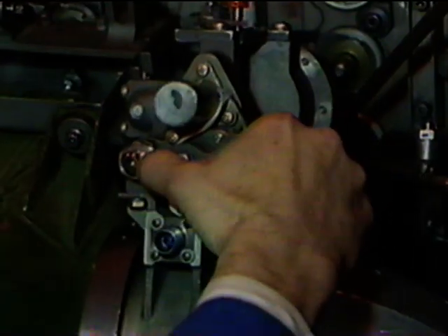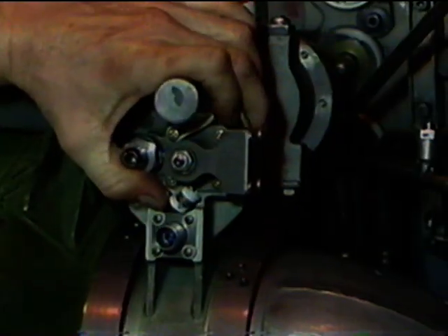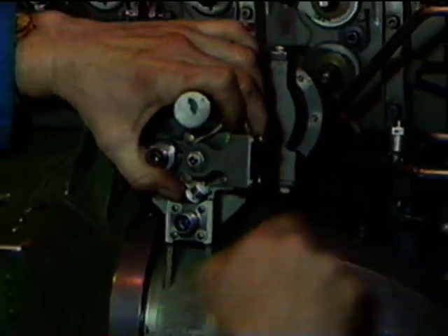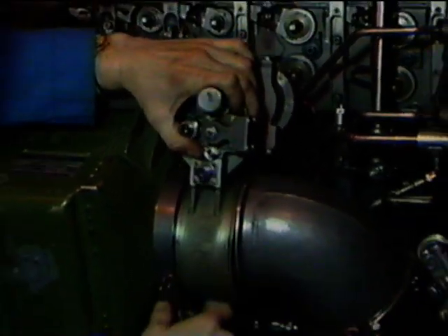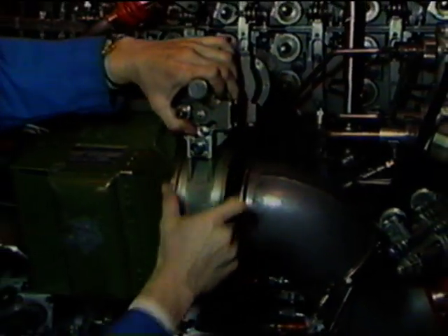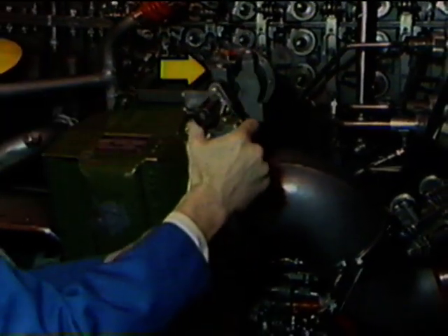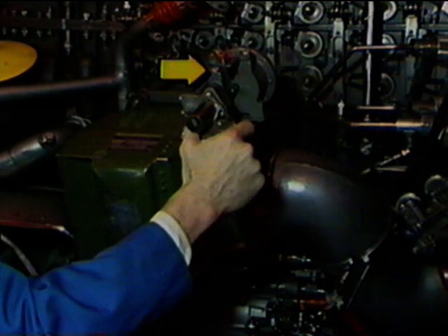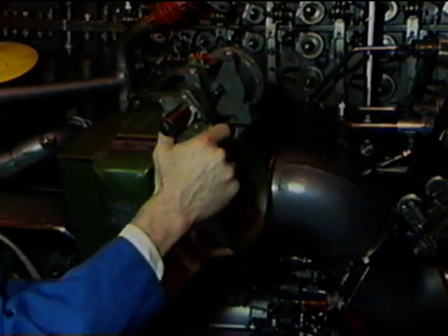Then, remove the couplings that attach the valve to the duct and to the cooler, and carefully remove the control valve. It may be necessary to manually lock the valve closed using the lockout lever and bolt provided to aid in the removal and installation process.